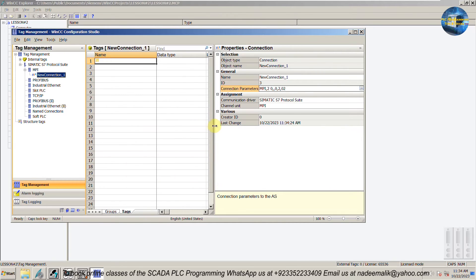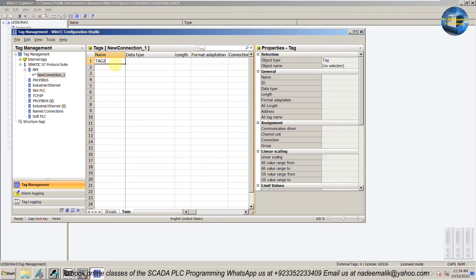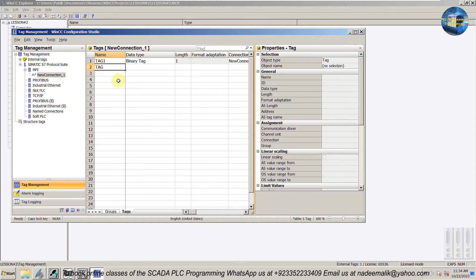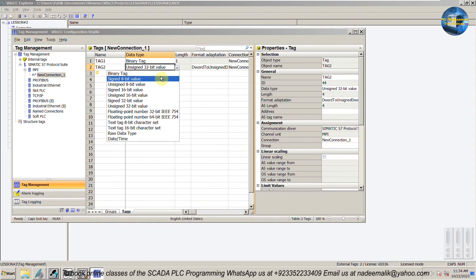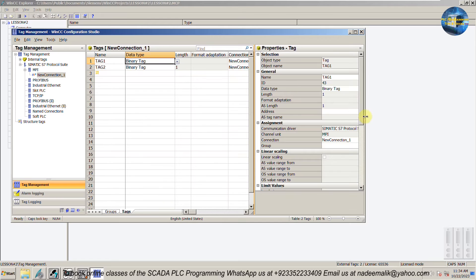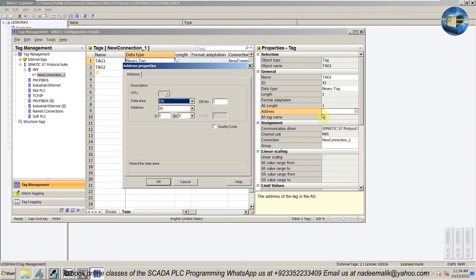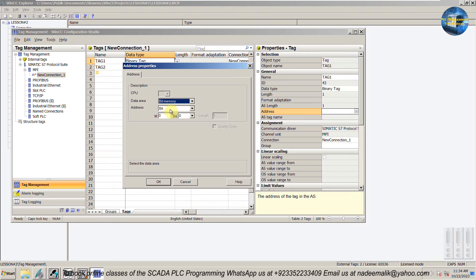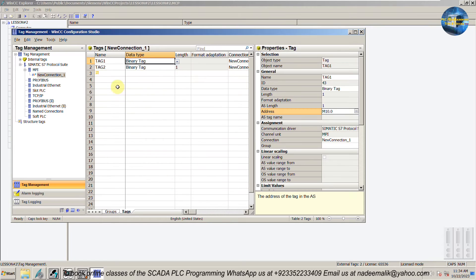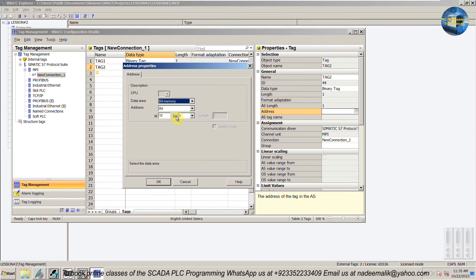We will make two new tags and set the data type of these tags as binary or boolean. Next we will open the address properties of the tags and set the data area as bit memory. Set the address as bit M10.0. For the second tag, follow the same procedure and set the address as bit M10.1.